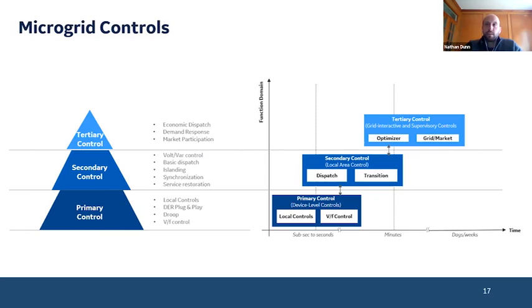Its main concern is taking in a schedule from the tertiary controller, reading what's going on in the system and the status of all the assets, and trying to comply with the tertiary controller, but its goal is to maintain reliability. So it's looking at live data, and if something changes, it reports it back up to the tertiary controller.